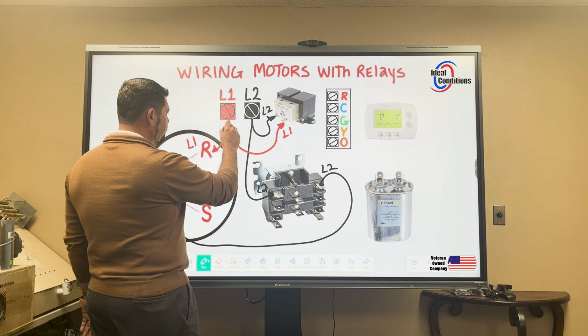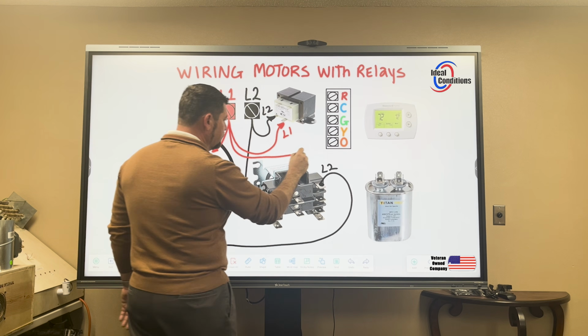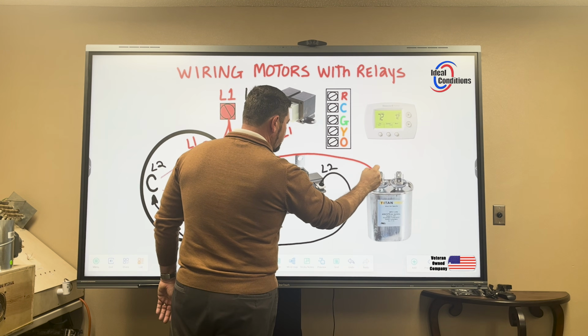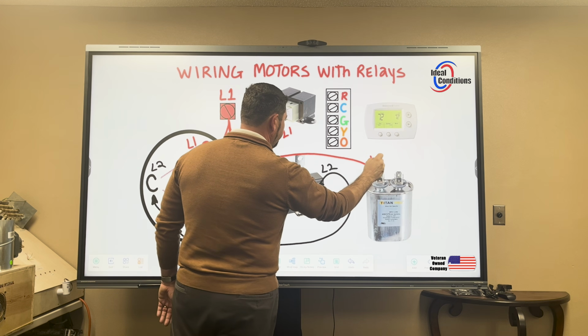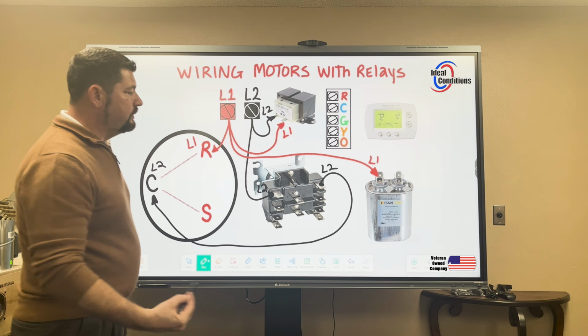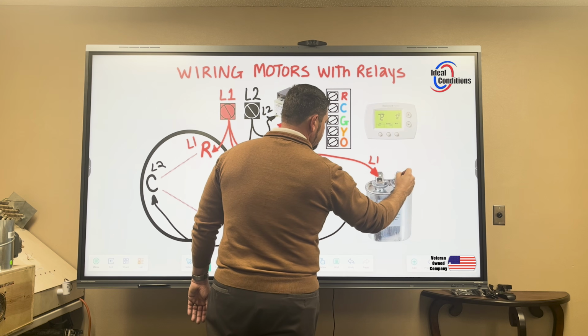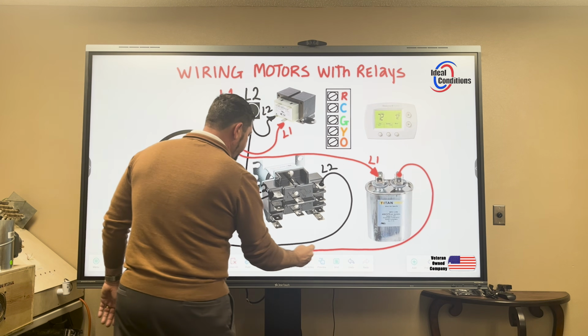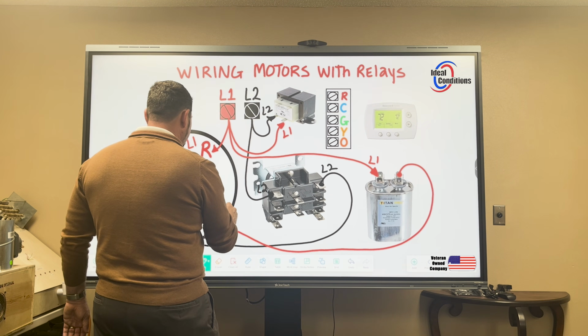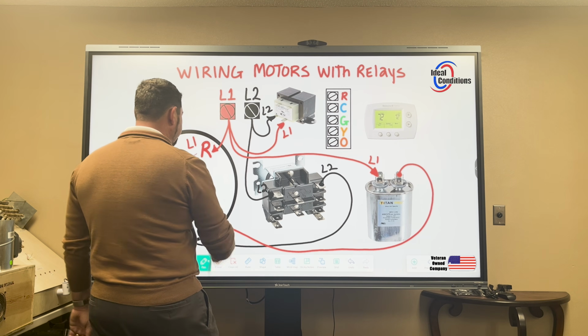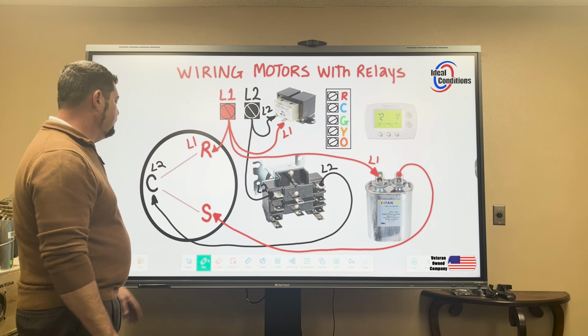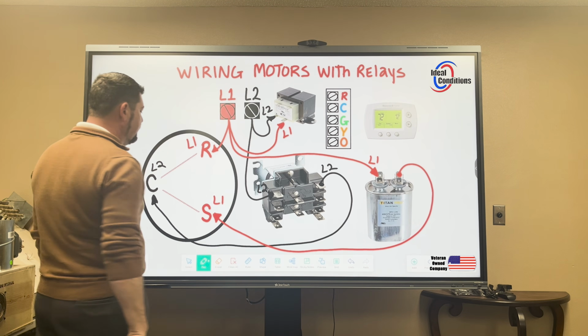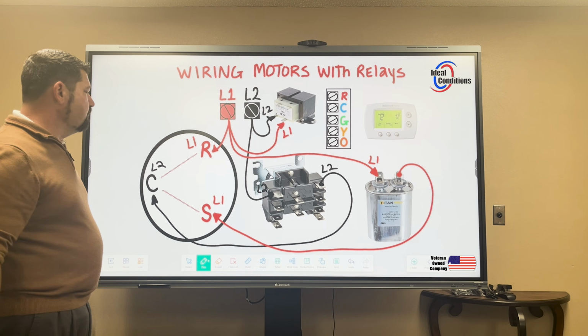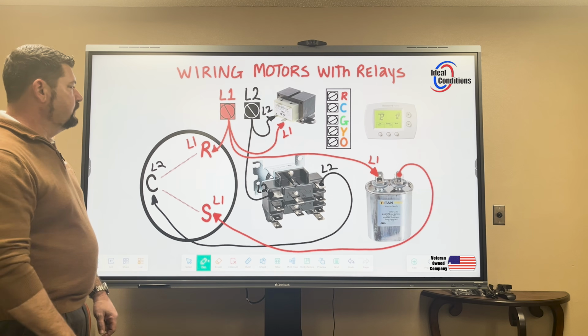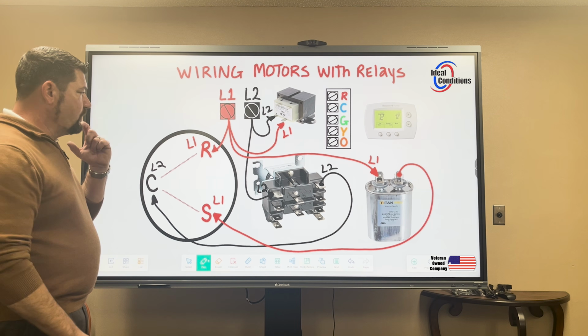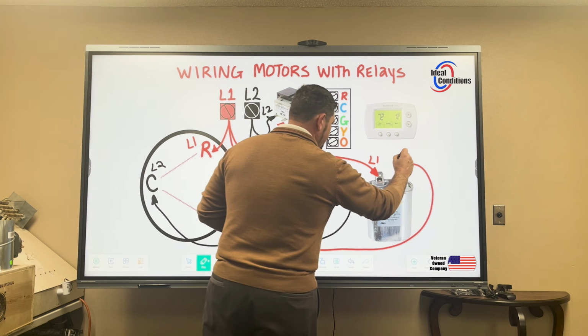And so what we'll do is we'll come over with L1, and we'll land it on one side of our run capacitor. We're going to go ahead and label this L1. And then we're going to come out of that run capacitor. All right, technically this is now our third leg of power. And now we have an independent leg on our start winding. And with this, even though it's still presently L1, we'll have polarity and that motor will turn on and run. So, of course, this is L1 here.